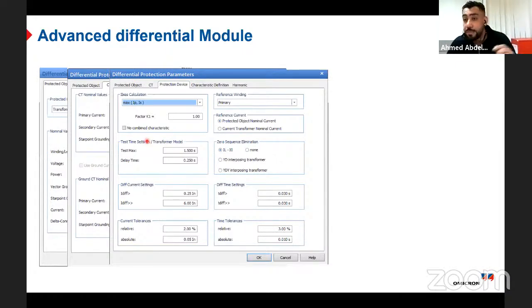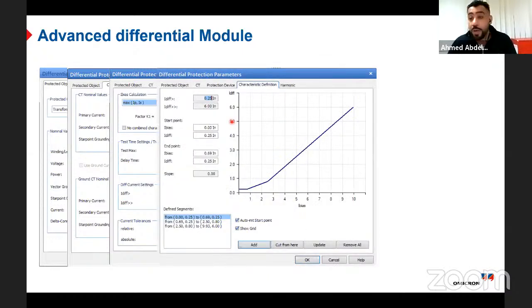Then you need to define the maximum operating time, the maximum differential current, the IDIFF greater, and you can define also what is the reference winding. Is it the star or is it the high voltage? Because some of the relays are looking for the star side, some of them looking for the high voltage regardless of whether it is delta or star. Afterward, you will go to the characteristic and you need to calculate the 3 points as we said, 0.1, 0.2, and 0.5. And then you will draw the characteristic and you will see the characteristic looks like that.